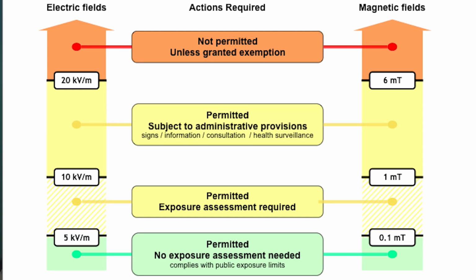You can see the actual numbers here. There's a hierarchy of levels. Down at the bottom, if you comply with the public exposure limits, no further action is needed. Then there are successive levels with successive actions attached. The level we normally follow is called the high action level, and that's 20 kilovolts per metre for electric fields and 6 millitesla for magnetic fields.